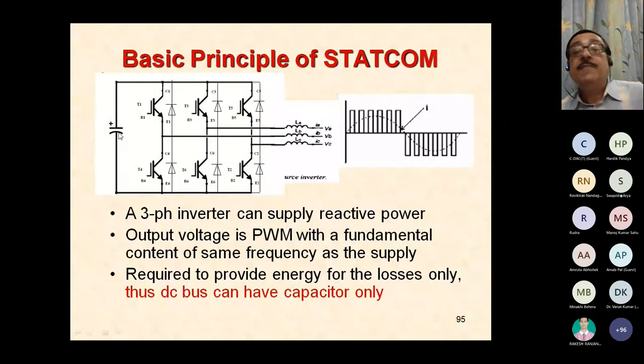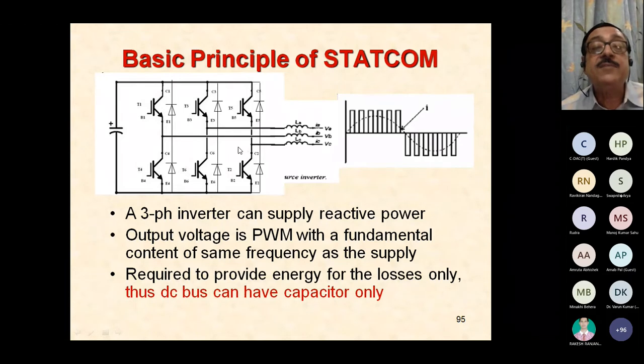We can use this system now as a STATCOM, where the template will be sinusoidal at fundamental frequency, but displaced by 90 degrees. And as I've explained earlier also, it can keep connected to the grid and supply reactive power, either lagging or leading with a quick response, and you need to have a capacitor only. The catch here is the system is not ideal.